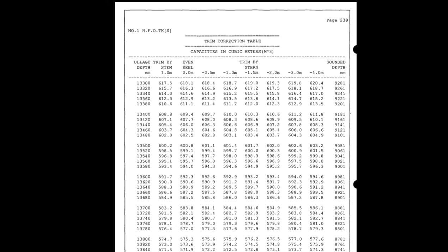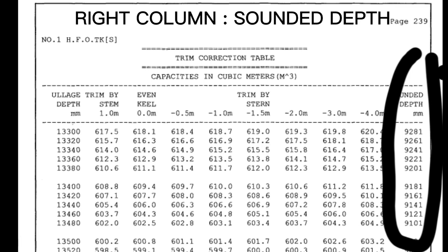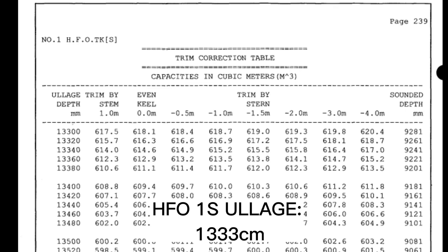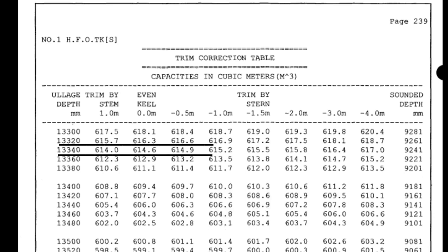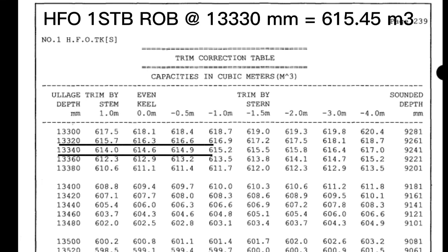Let's check the measured sounding of engine cadet. Left column: ullage depth. Right column: sounded depth. List and trim: zero. First is ullage of HFO Bunker Tank 1 starboard. Since 1333 cm is in between 13,320 and 13,340 mm, 1,333 cm is between 616.3 and 614.6 cubic meter. HFO 1 STB ROB at 13,330 mm equals 615.45 meters cubed.